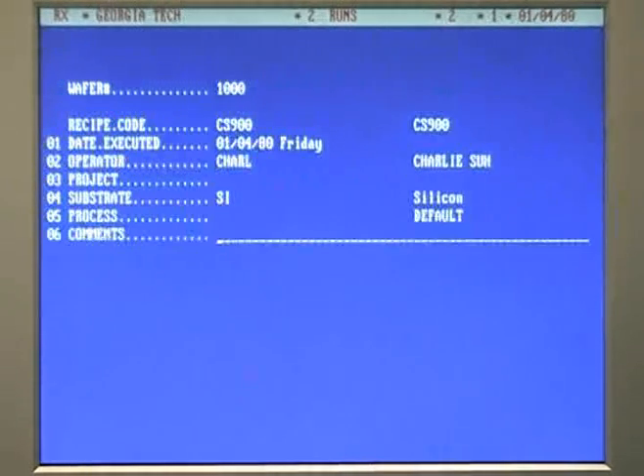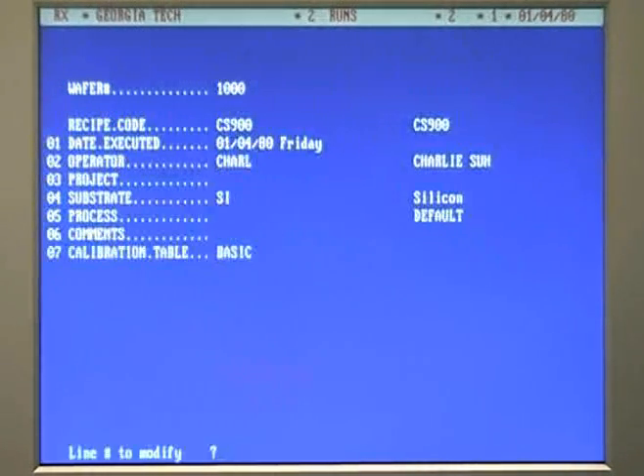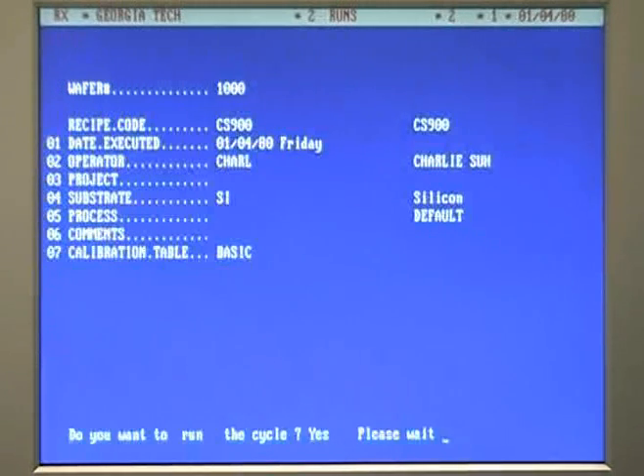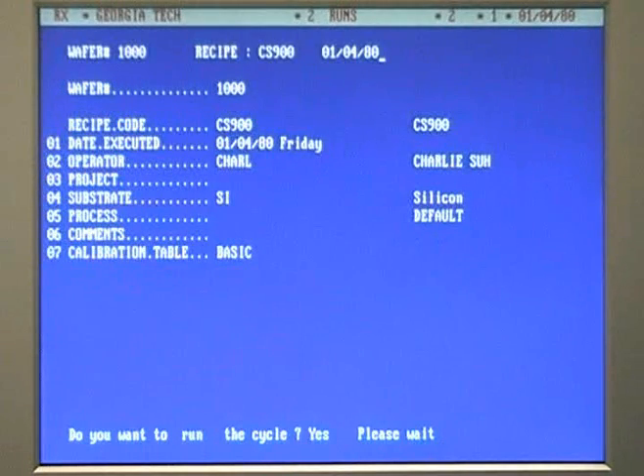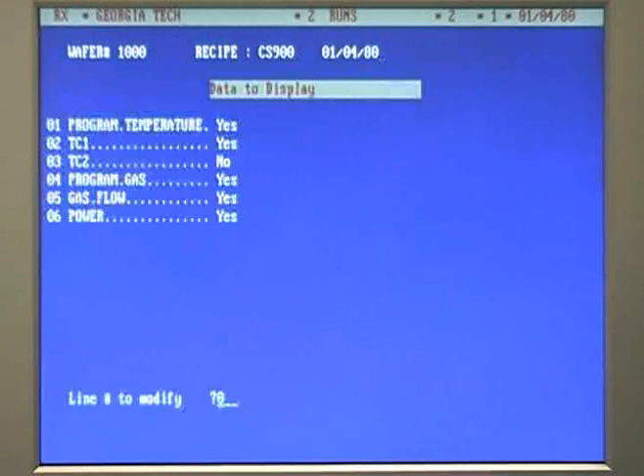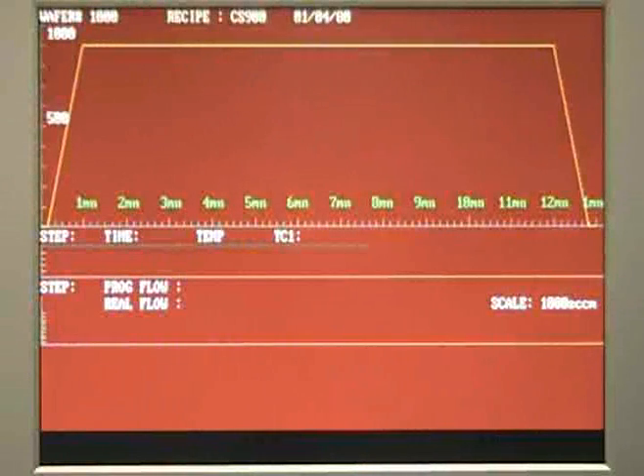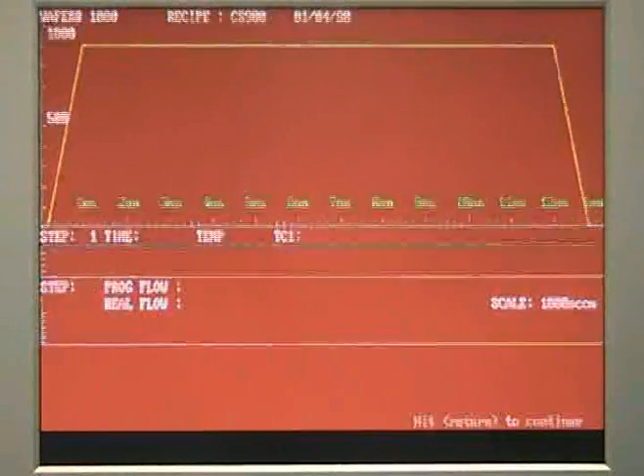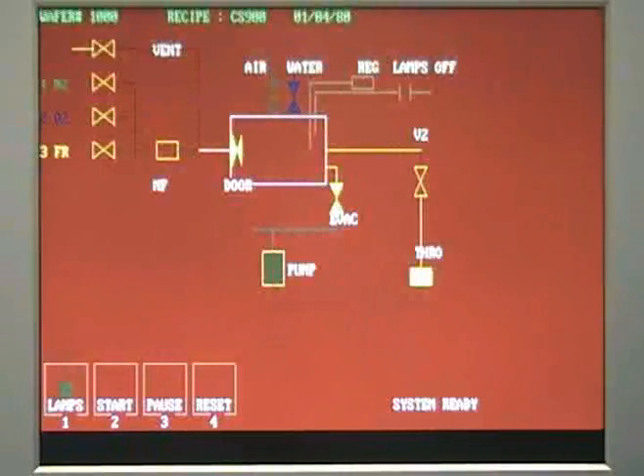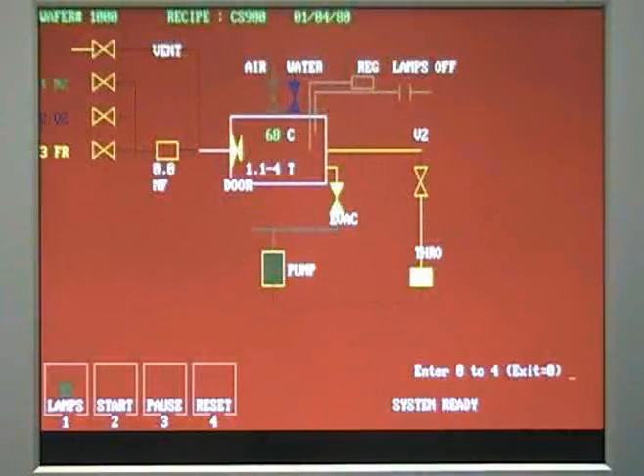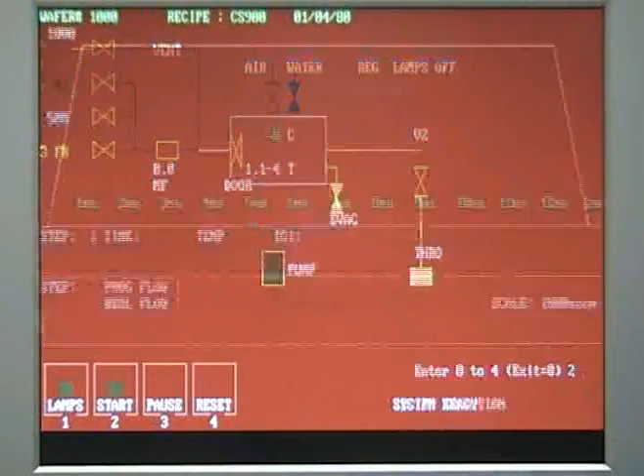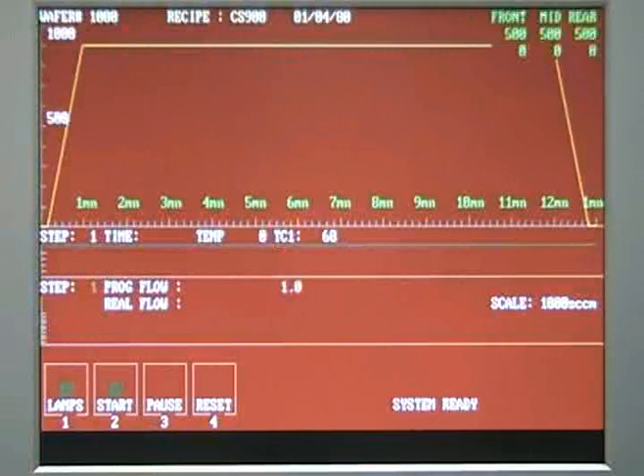When you get to the bottom of the screen, you will be asked which line you want to change. If you want to change anything, enter the appropriate number. If everything is okay, enter 0. There will be a few more screens of options after this one. You may accept the default values by pressing enter. After this, you will see a graph of parameters for the recipe you are about to run. Make sure that the recipe is correct, then press enter. Check to see if the readings on the temperature gauge on the screen and the handheld thermocouple gauge are correct. They should be about room temperature. After a few seconds, you will be able to select 2 for start. The recipe will then run.